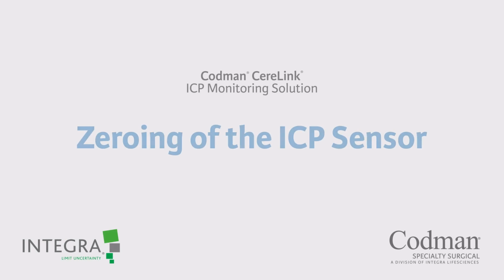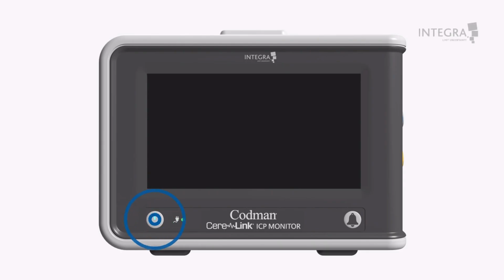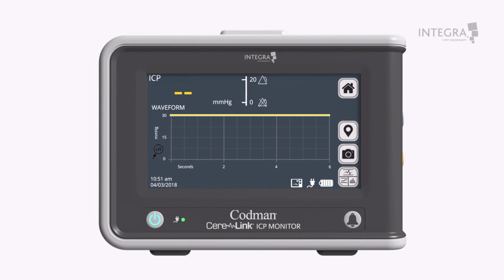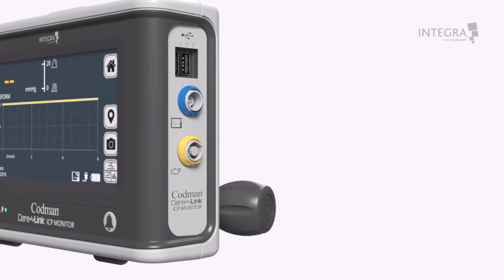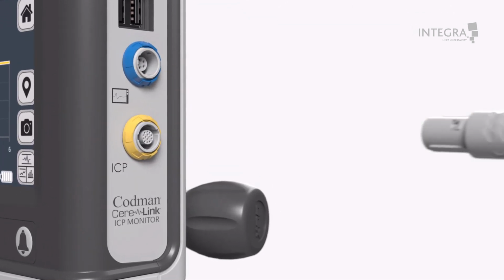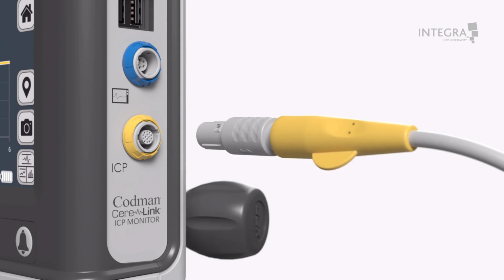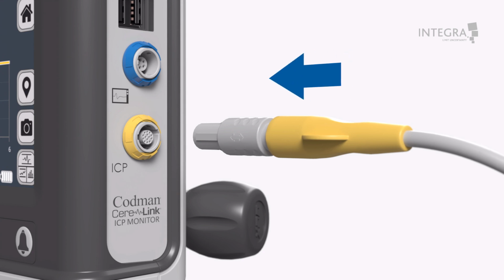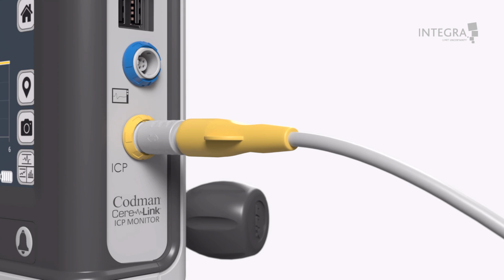1. Zeroing of the ICP sensor. The ICP sensor must be zeroed to atmospheric pressure prior to implantation. First, switch on the monitor. Connect the ICP extension cable to the yellow connector on the CereLink. The extension cable connector tab and arrows should face forward, in the same direction as the CereLink screen. Push the yellow connector into the yellow port until you hear a click.